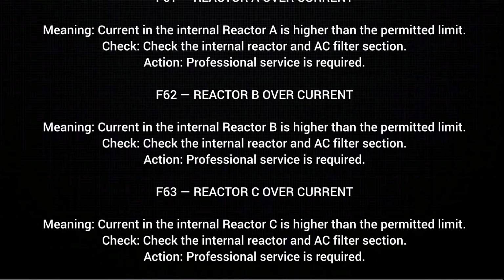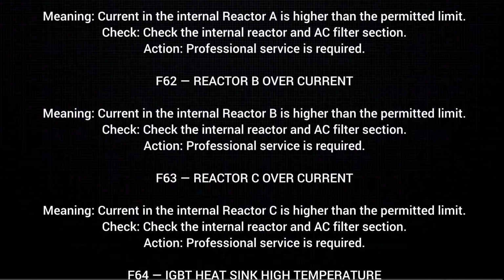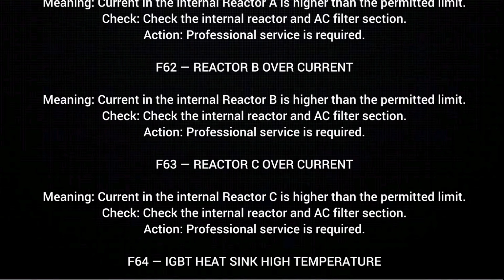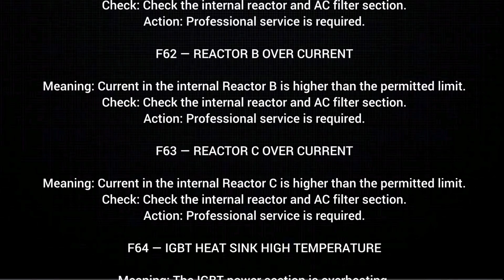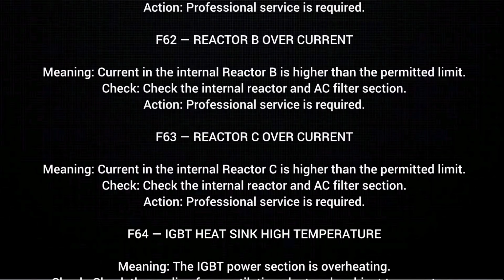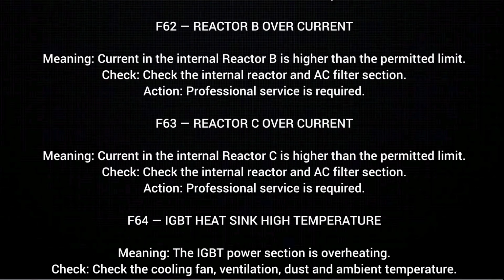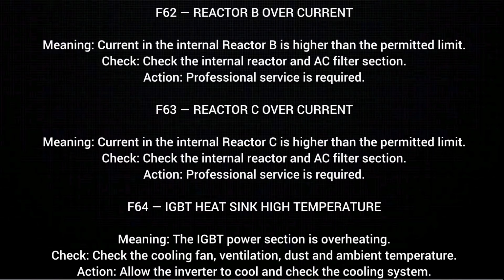F64. IGBT heat sink high temperature, meaning the IGBT power section is overheating. Check. Check the cooling fan, ventilation, dust and ambient temperature. Action. Allow the inverter to cool and check the cooling system.